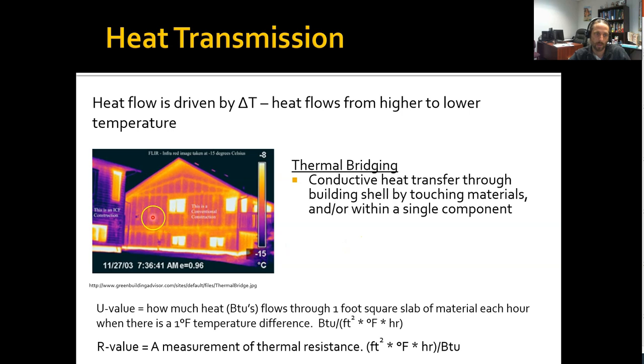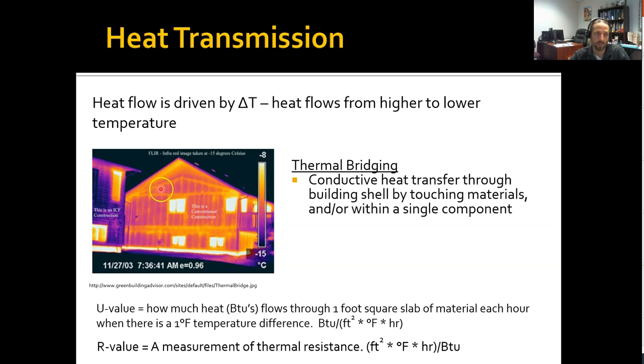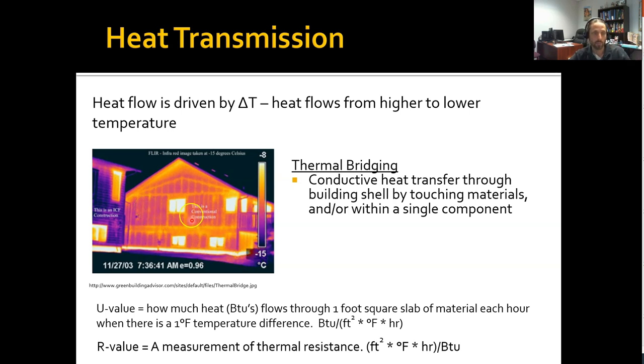This becomes really important for buildings — almost all buildings have this kind of stick framing, with different building components made out of wood. Wood does not have very good insulating value, whereas insulation does have pretty decent insulating value. These stripes you see here are the wood — you can actually see the framing. This is through an infrared camera that shows temperature — it's the temperature of the outside of the house. These lines are warmer where the framing is because the heat is escaping. You're outside on a cold day, and heat is escaping from the building through the framing, whereas through the insulation not much is getting out.